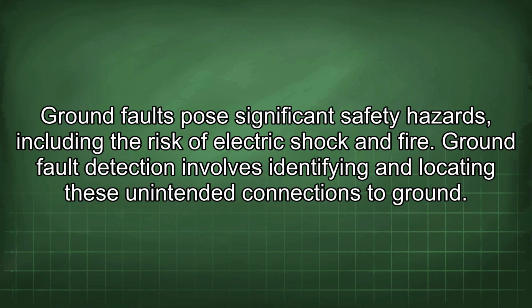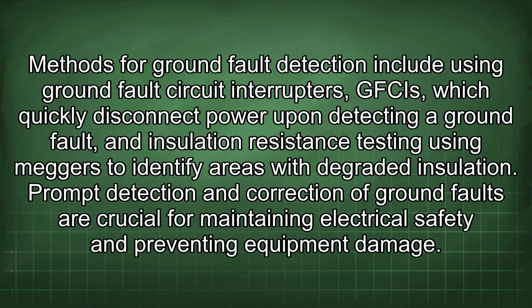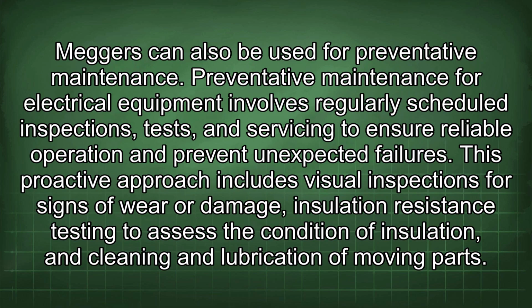Ground fault detection involves identifying and locating these unintended connections to ground. Methods for ground fault detection include using ground fault circuit interrupters, GFCIs, which quickly disconnect power upon detecting a ground fault, and insulation resistance testing using Meggers to identify areas with degraded insulation. Prompt detection and correction of ground faults are crucial for maintaining electrical safety and preventing equipment damage. Meggers can also be used for preventative maintenance.